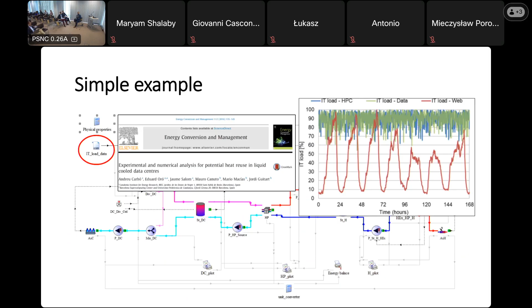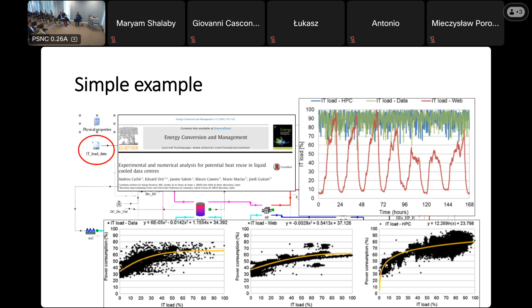What's also very interesting for me, but for sure needs more analysis, is that they also give the IT load in percentage of power consumption for a given type of load. You can see that, for example, high performance computing has the most power consumption, reaching almost 80% in this yellow approximation, while the other types of tasks, web and data, go below 70%. So if I understand correctly, given the same IT load but a different type, you will need less cooling to perform it. I use this approach in this simple example.